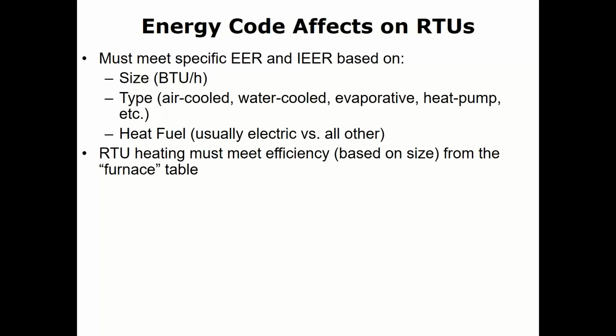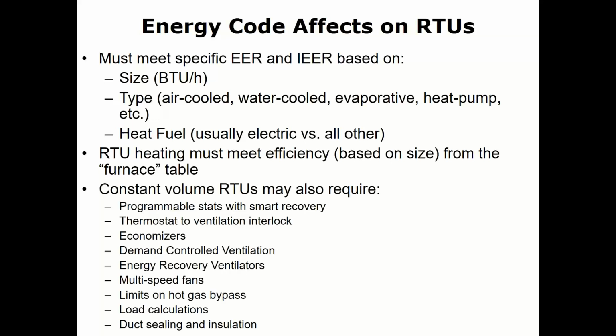So the effects that energy code is going to have on my equipment, it's going to affect my size. We're going to talk about all these individually, but it's going to affect the size of my equipment. It's going to affect the efficiency of both my cooling and my heating. It's going to determine what kind of thermostats I have to use and how I have to set my thermostats up. It's going to force me into economizers and some unique control requirements of the economizer. It might force me into demand ventilation, ERVs, VFDs on my fans. I have to do load calcs. I got to seal ducts. There's going to be a lot of things that it forces me to do here. And we're going to talk about some of those things as we dive into each one of these technologies.